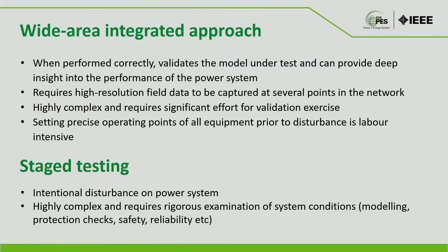Some examples of wide area integration. So one on the right side is from the System Black event that happened in Australia in 2016, where you can see the dotted lines are HSM - high speed monitoring devices, so it's like high resolution field data. Dotted line, then grayish line is the RMS model, and this darker line is the EMT model.